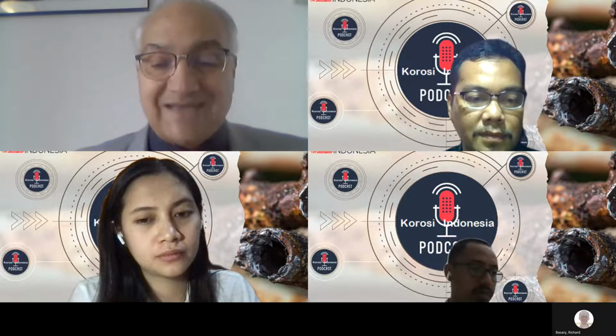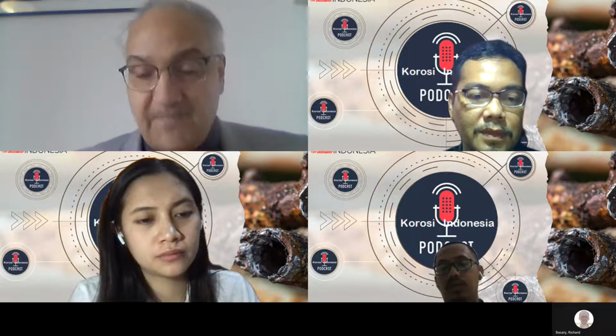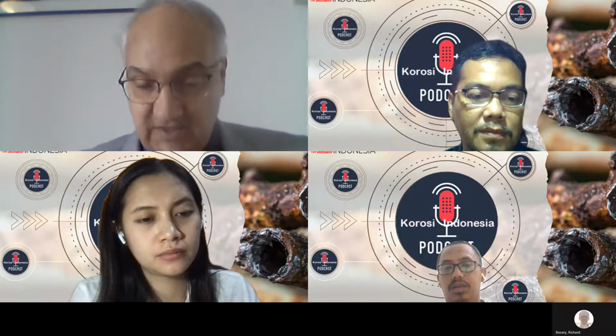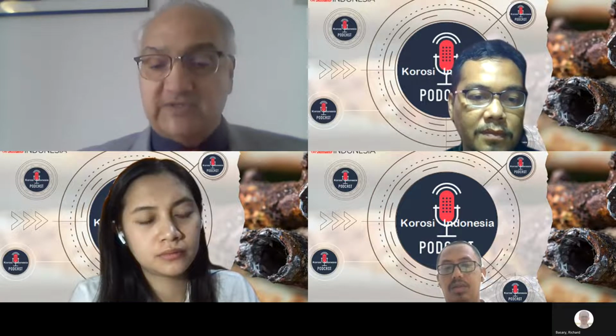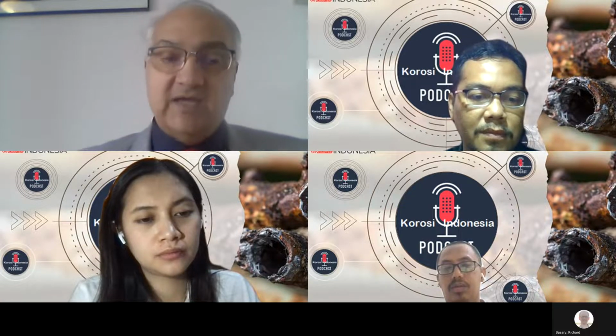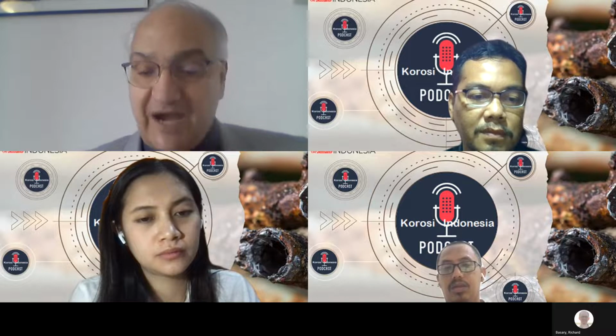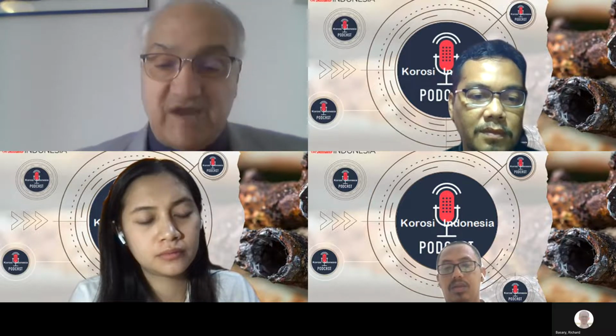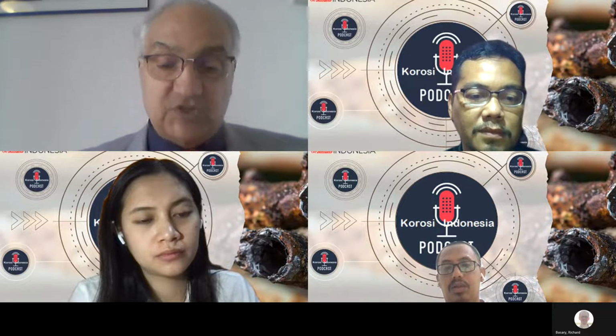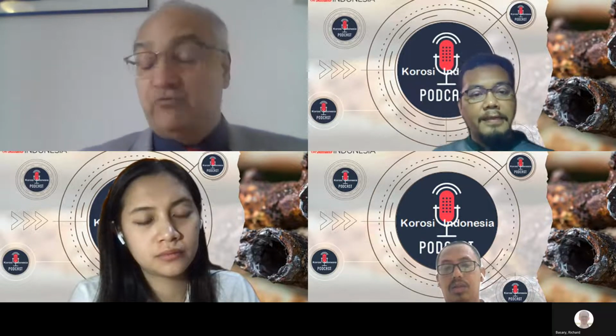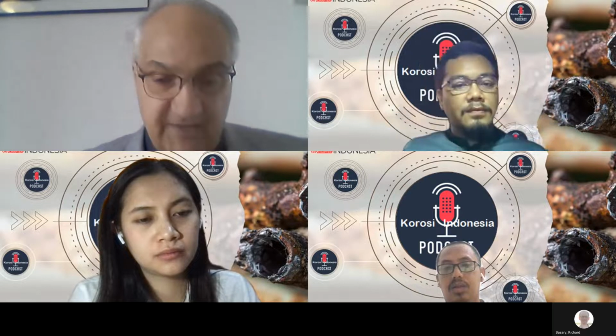So if you have somewhere stagnant water in liquid form, in contact with rough surfaces, particularly surfaces after practices such as welding, on which post-weld treatment has not been carried out or has not been carried out completely, this could be one of the points in which the likelihood or risk of MIC could be high.